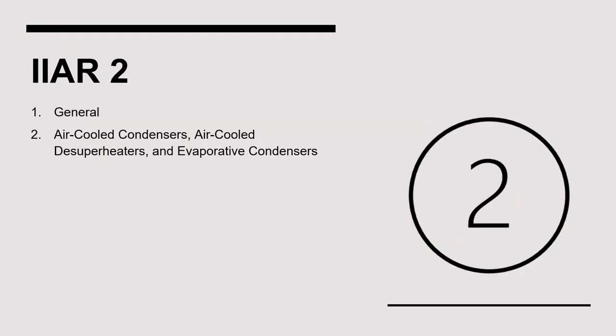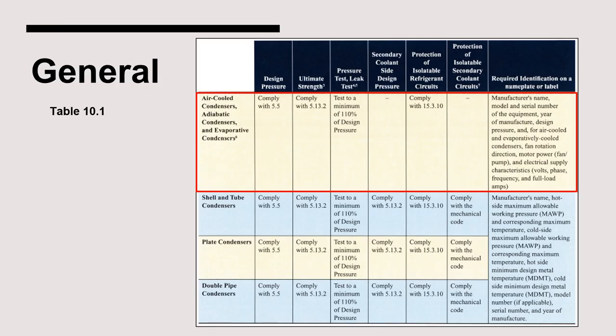Let's start with IIAR Standard 2, which addresses general aspects of condensers. We'll also examine requirements for air-cooled condensers, air-cooled desuperheaters, and evaporative condensers in Chapter 10 of IIAR 2. General requirements for various types of condensers are contained in Table 10.1. These requirements include design pressure, ultimate strength, pressure and leak testing, secondary coolant side design pressure, protection of isolatable refrigerant circuits, protection of isolatable secondary coolant circuits, and required identification on a nameplate or label. Regarding condenser nameplates, these must be equipped with the manufacturer's name, model, and serial number of the equipment, year of manufacture, and design pressure. Air-cooled and evaporatively cooled condensers must also include fan rotation direction, motor power, and electrical supply characteristics.